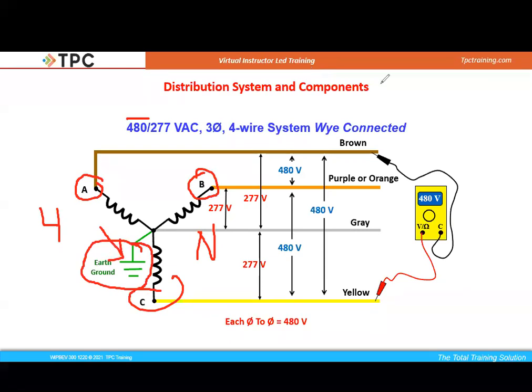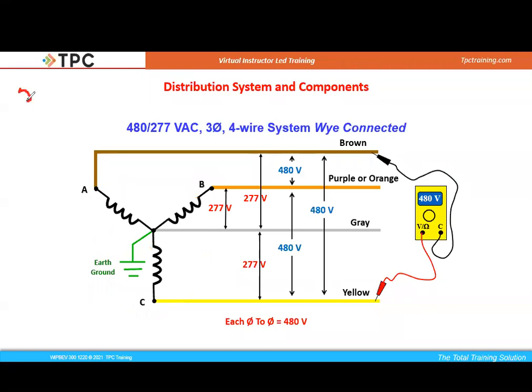And so when we do that, we might have out here a three-phase motor somewhere. If we have that three-phase motor, that is not going to need a neutral. And so we would just bring phase A, phase B, phase C to that three-phase motor, and our motor would turn. No question about it. But we might want to pull some single phase loads off this. And to pull a single phase load off, all I have to do is get one energized phase and my neutral. In this case, you can see that when we go from any phase to the neutral, we get 277 volts. So we use that a lot for industrial and commercial lighting. And we'll pull our lighting off of that system.